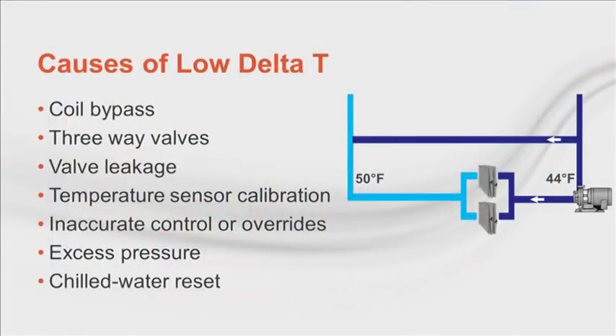And the final culprit is chilled water reset. By this I mean anything that makes the temperature supplied to the valve warmer than design. This could be due to deficit flow or a control optimization that's doing more harm than good. Getting to the bottom of the causes of your poor DeltaT is crucial, but it isn't glamorous work, so it's often avoided. So what can we do if we can't resolve all of the low DeltaT problems? Can we minimize its effects on our chilled water system? There are 3 effects: excess pump energy, loss of chiller capacity, and as a result, too many chillers online.